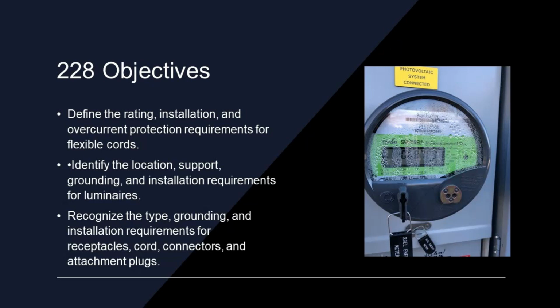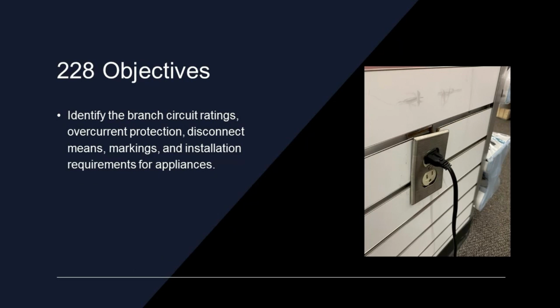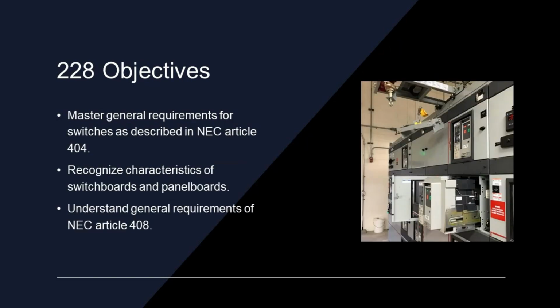All right, we are going to define the rating, installation, and overcurrent protection requirements for flexible cords. Location, support, grounding, and installation requirements for luminaires. Types of grounding and installation requirements for receptacles, cords, connectors, and attachment plugs. We're going to identify the branch circuit ratings, overcurrent protection, disconnect means, markings, and installation requirements for appliances. We also have general switches in Article 404. We're going to recognize characteristics of switchboards and panelboards, and understand the general requirements of NEC Article 408.